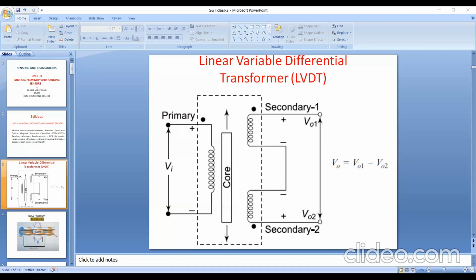With respect to the movement of the core, there is a change in the magnetic field and a change in the electric voltage. So the displacement of the core is converted into an electrical signal. And the third case: the core is moved towards the left of the null position. Here, when the core is to the left of the null position, more flux is linked with S1 compared to S2. So ES1 is greater than ES2. The voltage generated is E0 equal to ES1 minus ES2. Since ES1 is greater, we obtain a positive voltage.